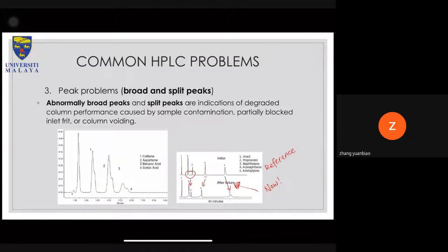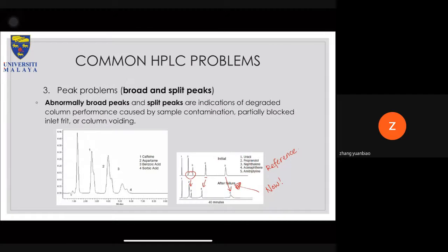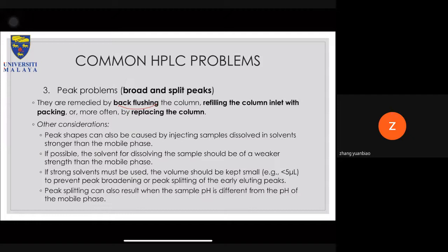Otherwise, if the drift is very minor, then you might want to investigate something else, such as your solvent concentration and whatnot. Okay, so if the column is the main culprit, you can easily fix it by back flushing. What it means is that if you have used an HPLC, a column has its own designated inlet and outlet. Okay, so you normally don't keep on switching them.